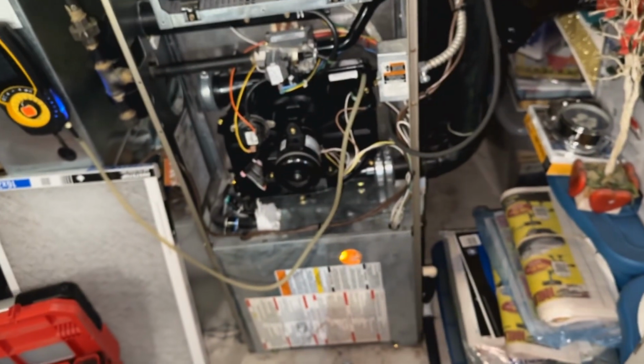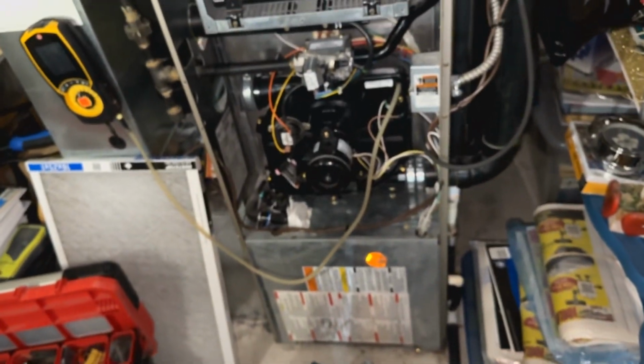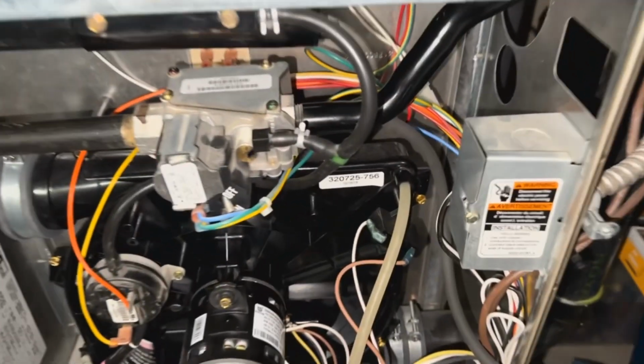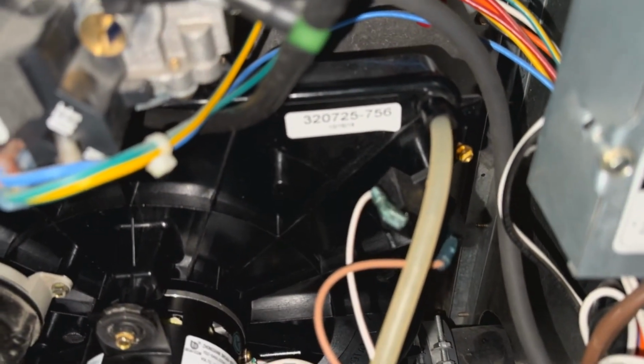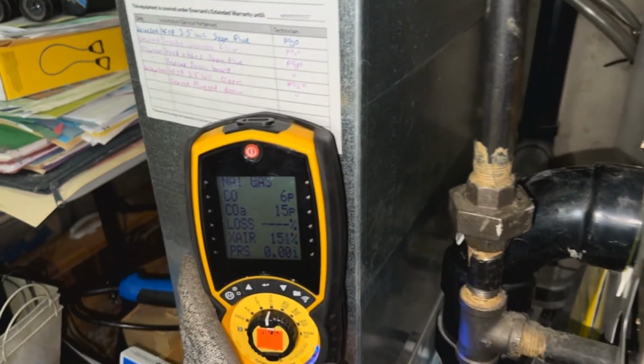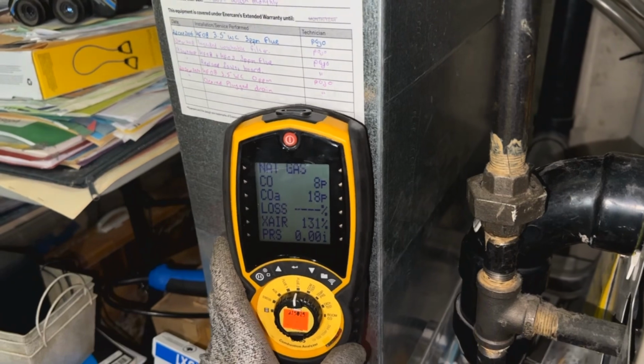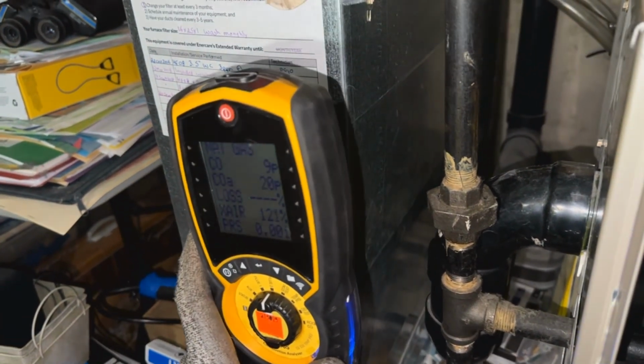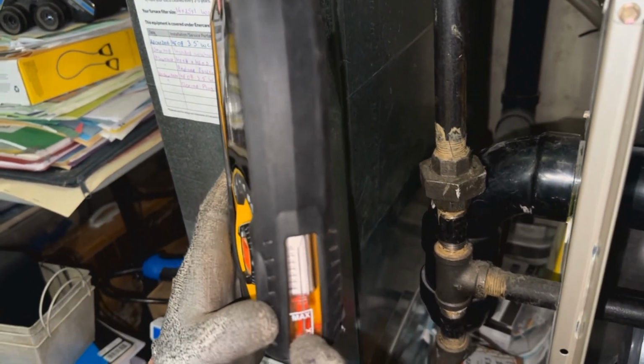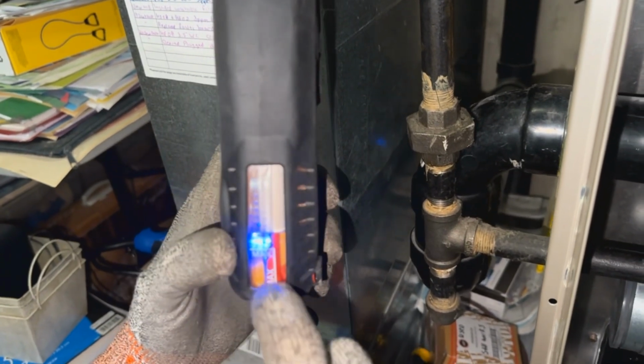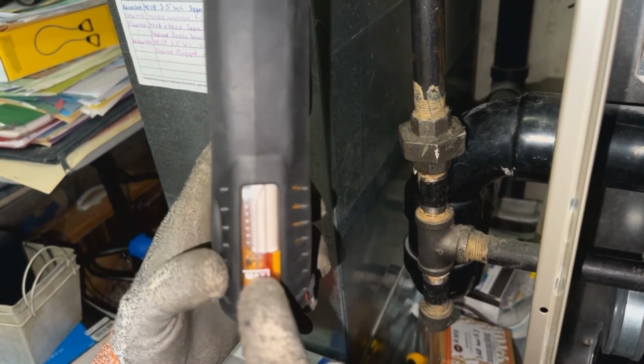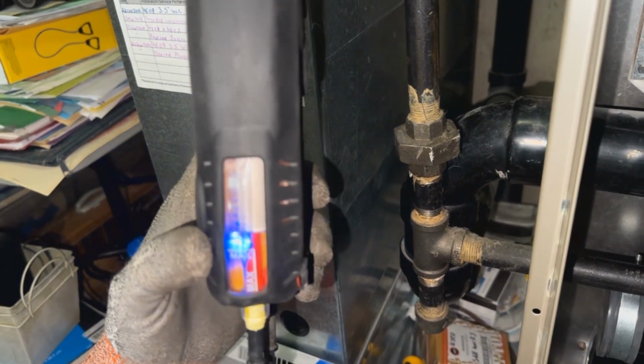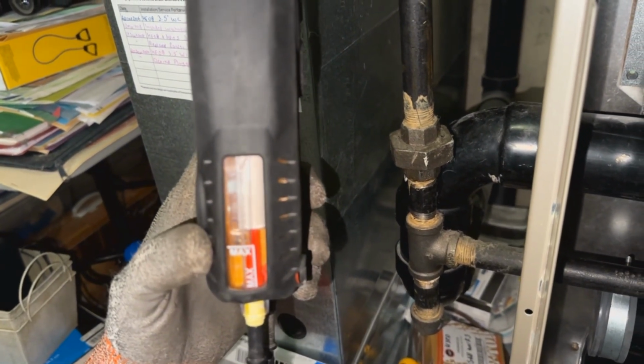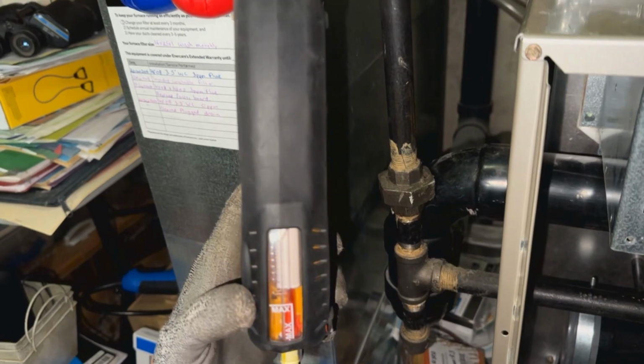We'll just do a quick CO test, just make sure that we're around the same number outside. So the other spot to check CO, like I mentioned earlier, is just off the venter motor. There's a little port. You just tie your hose in, then you get to see your CO reading. And a lot of the guys say don't check CO there because it can draw condensation up into my trap here. But if you look, it's quite a bit before that water level is going to go up to the filter. So I always monitor it, make sure I'm not getting water in there. If I am, I drain that water out.